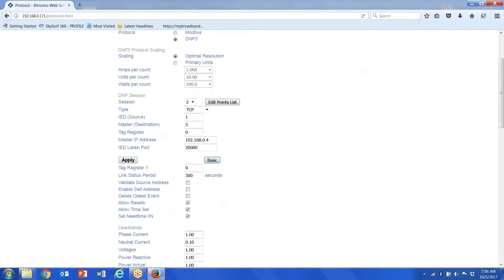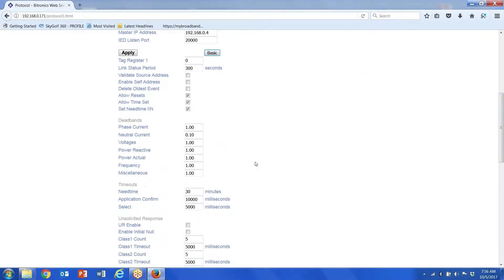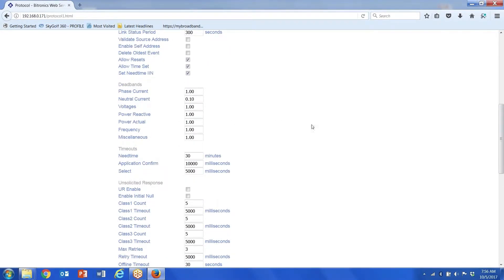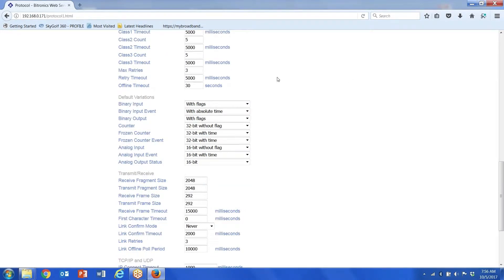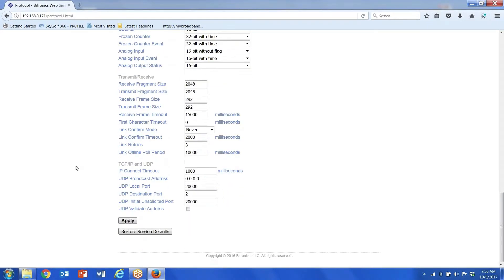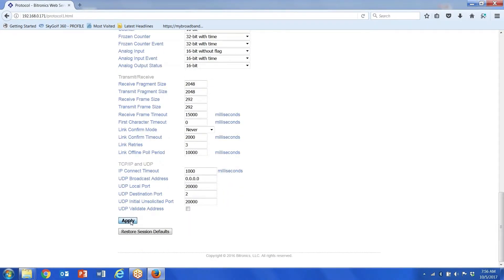I can go back in and select the Advanced tab. The Advanced tab allows me to go in and set dead bands if I want to assign change events. For counters, the drop-down menu here — the factory default is 32-bit without flag.